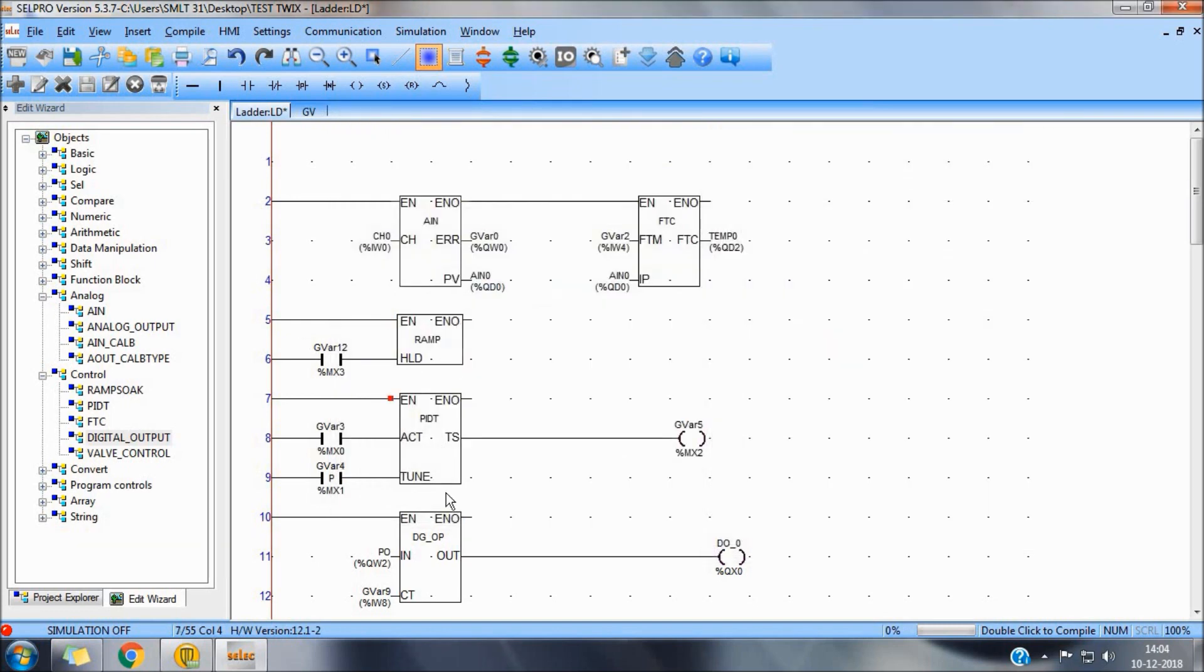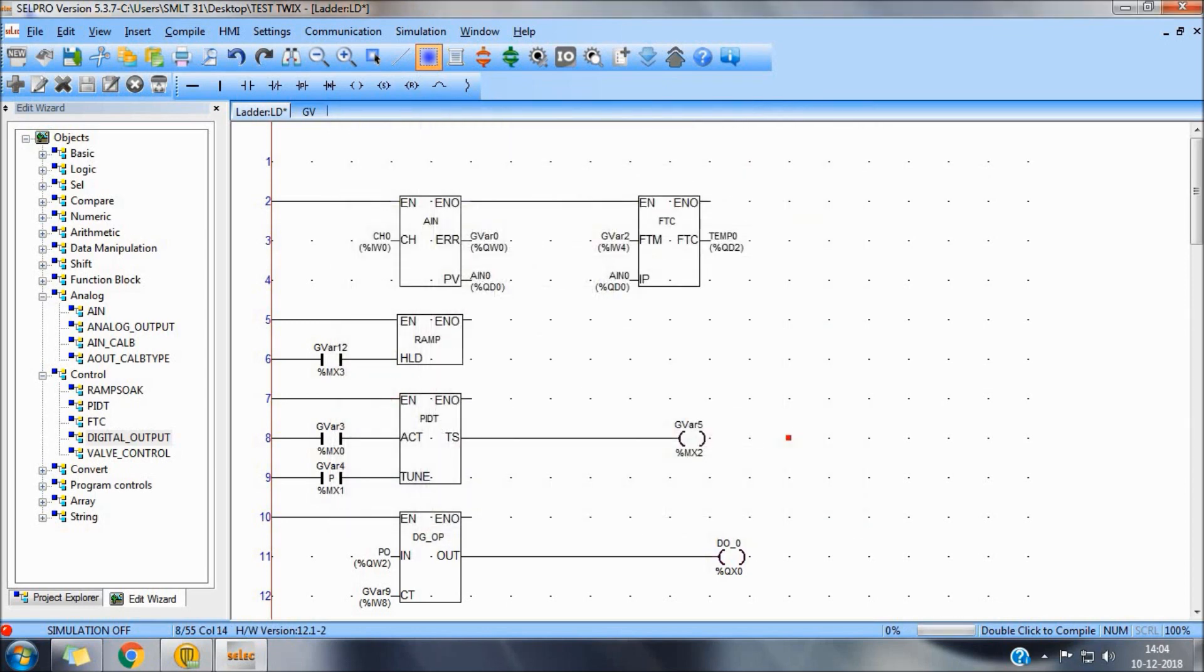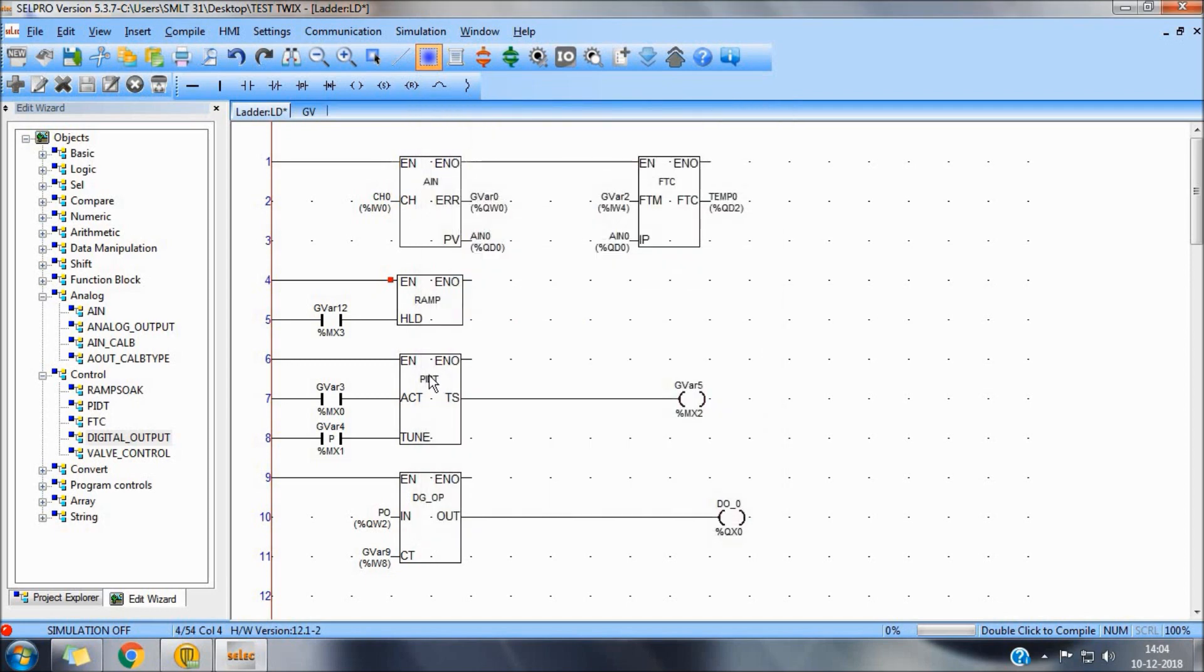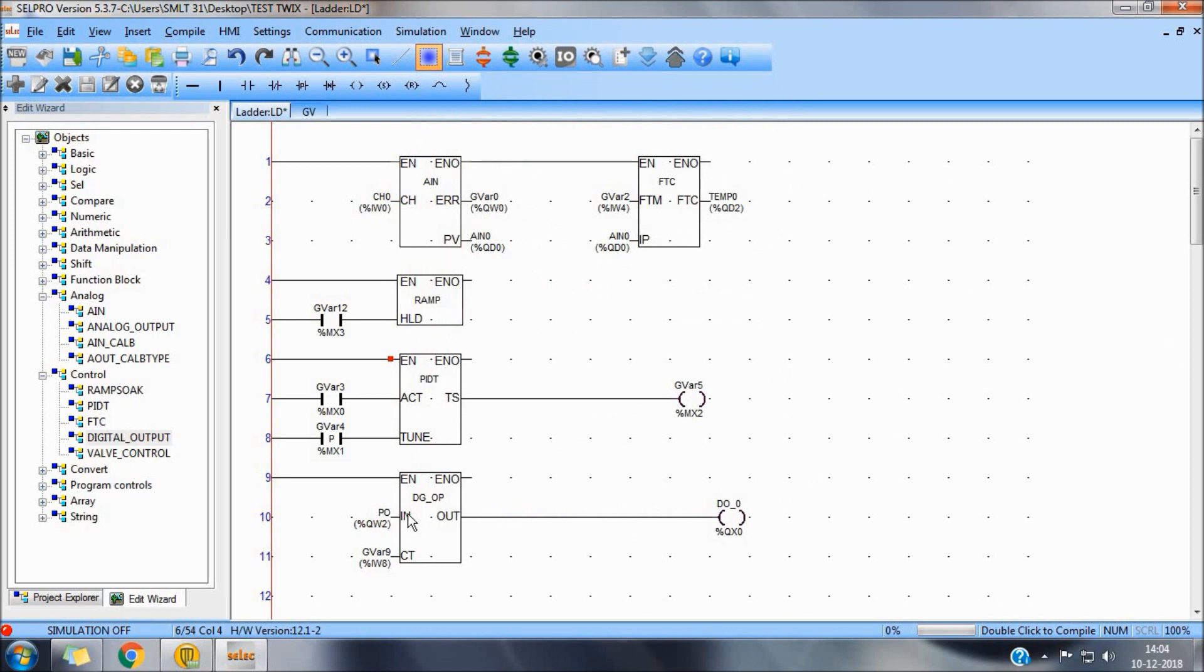To control output through a RAMSOAK block. We will just need to change the setpoint to RAMP setpoint. As per these values, this RAMPSOAK will start increasing the output from initial RAMP to setpoint, which will be fed to the PID. Accordingly PID will generate a percentage output to drive or to control the digital output. So this is a basic representation and operation of a PIDT block along with a RAMPSOAK.